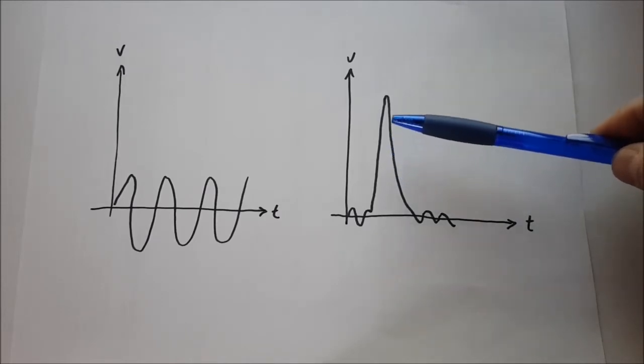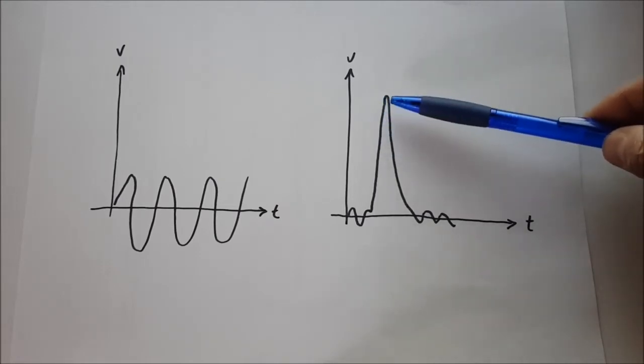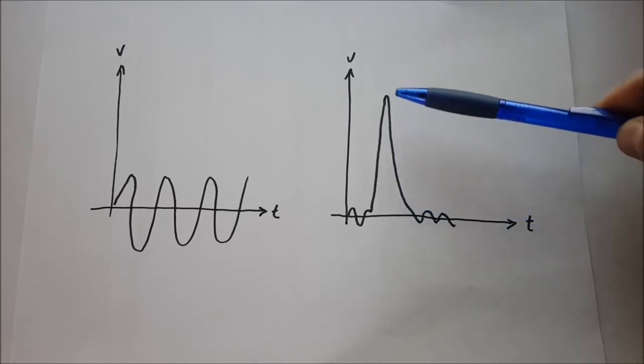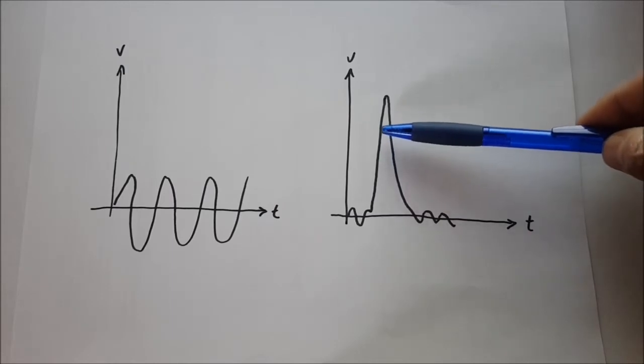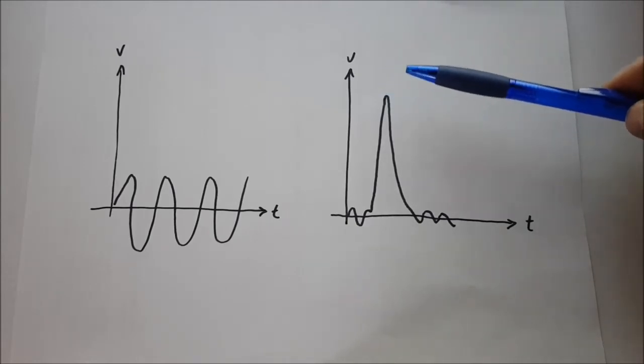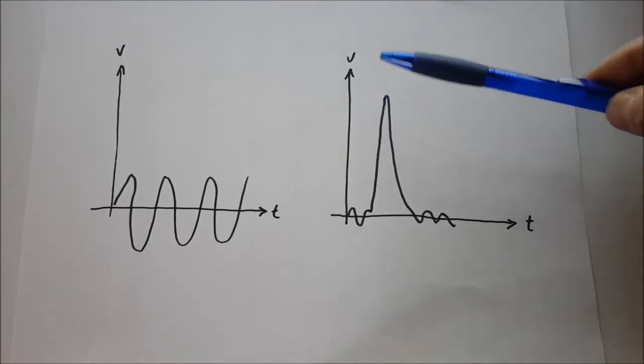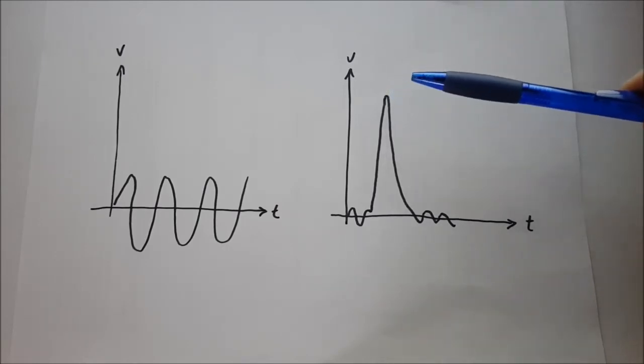But now in this case, we know we are isolated, so how can this energy go back to the ground? Well, it can only go to ground by breaching the insulation somewhere. So the voltage will rise, rise, rise, rise until the moment that the insulation cannot withstand the high voltage anymore. It will breach the insulation somewhere in an electrical appliance or inside the wiring itself.